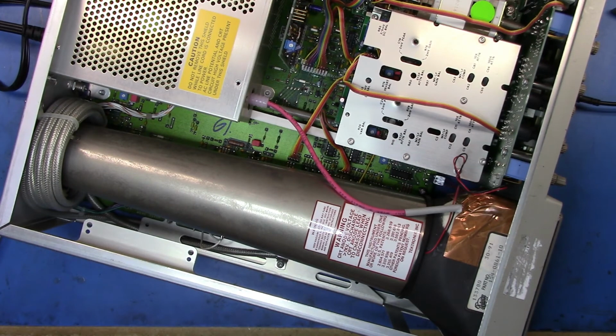Typically the third-party guys have 2 types of calibration. They will do just the calibration approach, which is go out, test it, hey, it doesn't work, they'll write fails calibration and return the unit to you, or they'll do calibration and adjustment. So in this case, I'm guessing that the FAA just sent these out for calibration, and when they came back and said they weren't calibrated, they then wrote them off, whereas had they sent them out for calibration and adjustments, the Bionetics guys probably would have popped the covers off, calibrated them, found they were out, tweaked those things, and then sent them back and passed them into calibration.